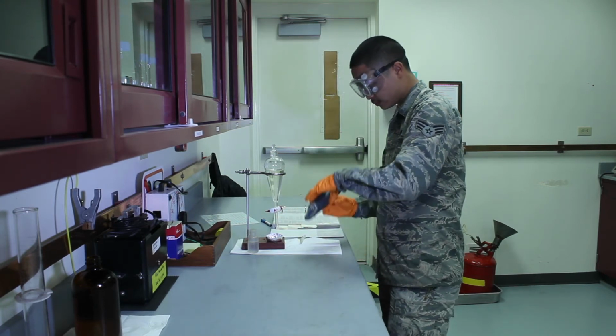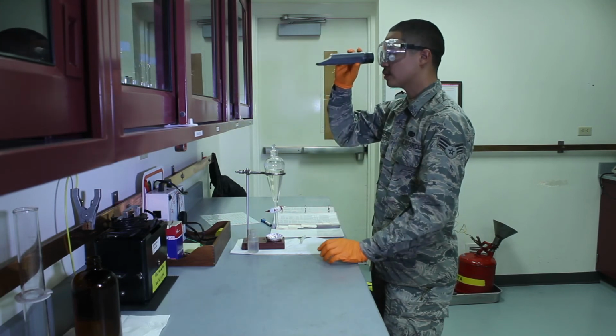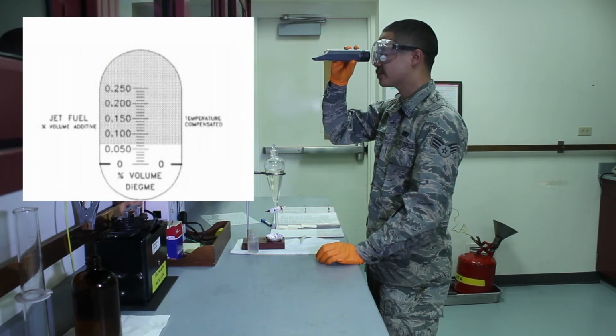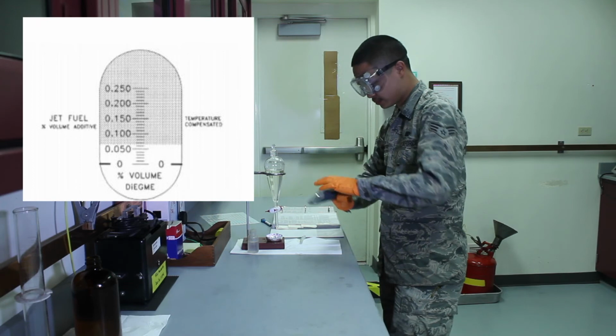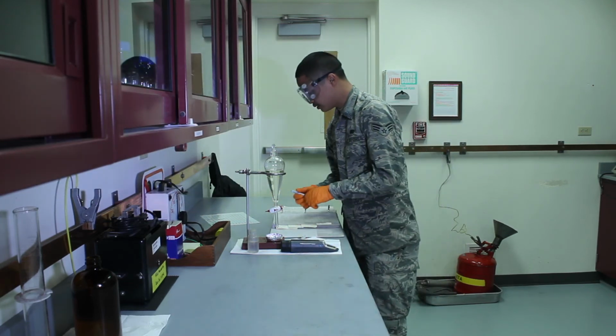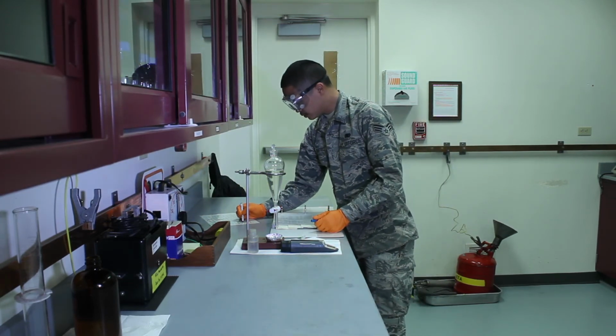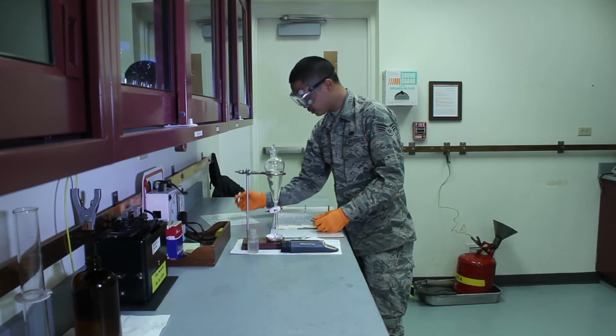Hold the instrument in a horizontal position, keeping the cover plate intact with the prism and the instrument. Point the instrument towards the light. Here you see again the measurement of 0.070 at the gray line. Record your results, properly dispose of the unused fuel and water, and as always, wash your dishes. Thanks for watching.